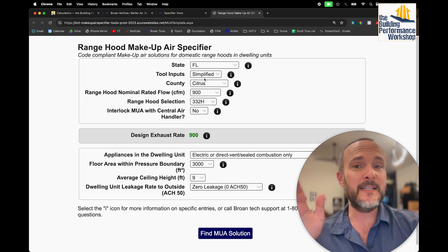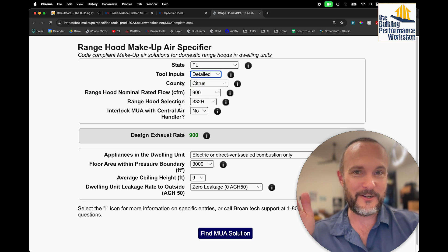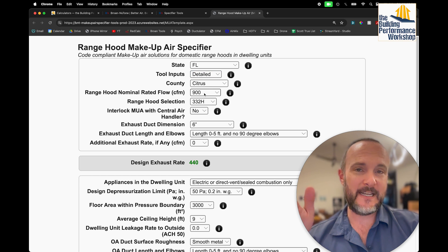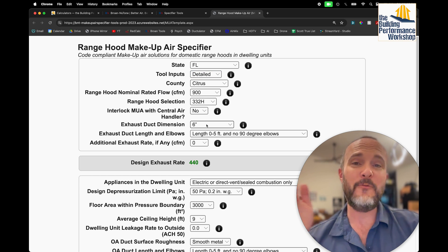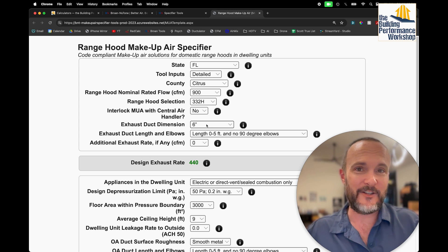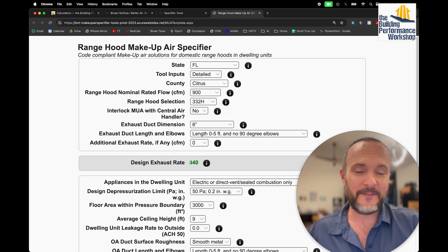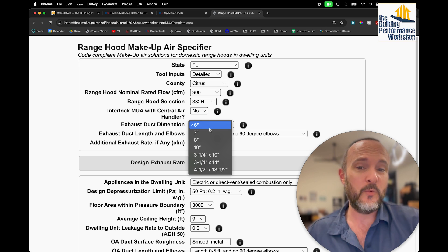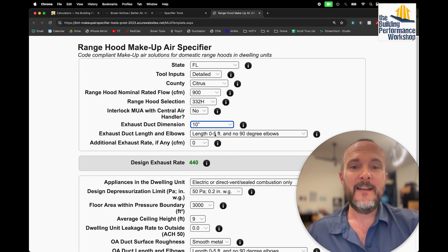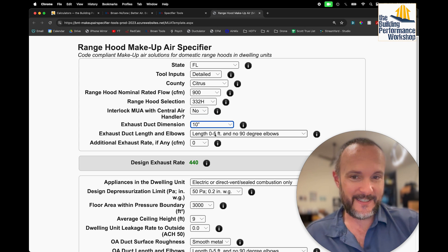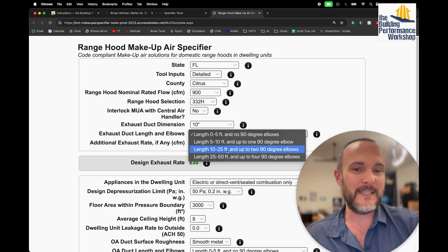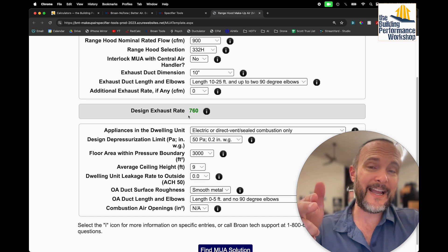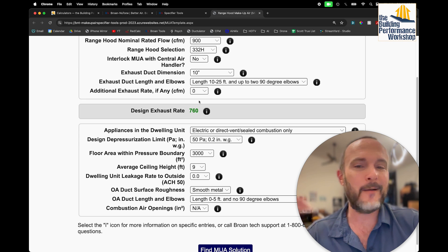Let's go back and use the detailed inputs, because this is really how life is going to work. So first of all, we've got our 900 CFM exhaust hood. How are we ducting that? If we duct it with the default 6-inch duct, this calculator knows enough to tell us that we're not going to get 900 out of it. We're not even going to get half that. We're going to get 440 CFM out of that. So we're going to have to duct this with 10-inch round, which is the correct answer. And then I want to put in how long this duct is, so that I can find out, like, let's just say it's going to run between 10 and 25 feet and have up to two 90-degree elbows on it. Out of that 900, even with a 10-inch duct on it, I'm only going to get 760 CFM.